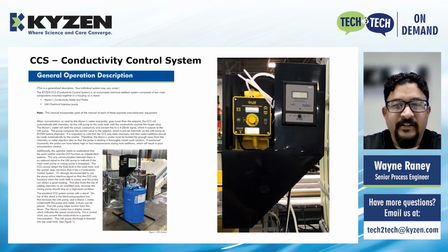The CCS is a Kyzen-made system which is used to regulate the concentration of an aqueous cleaning chemistry. The concentration can be determined by measuring the conductivity of the fluid. The picture on the right is the system, and the picture on the left is a system above a drum. When the conductivity goes below the set point, then the system will add chemistry with the yellow LMI pump. When the set point is reached, the addition is effectively stopped.